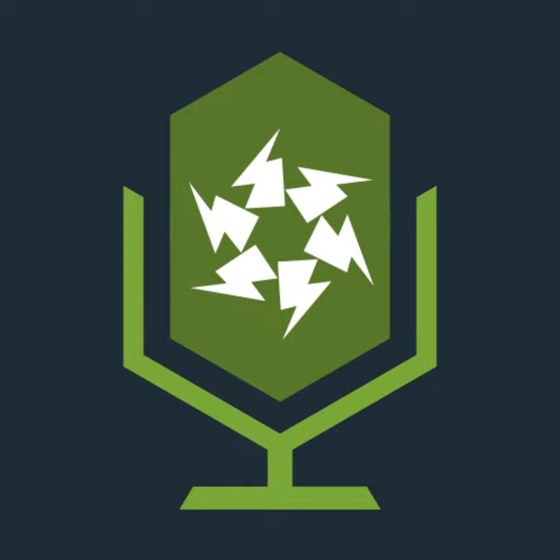Now, if it's on a 61009 with an RCD, then for an earth fault scenario, it's going to trip at 30 milliamp. So for all intents and purposes, 50 volts over IA of 30 milliamp is 50 over 0.03, which we said back in TT systems gives us 1667.